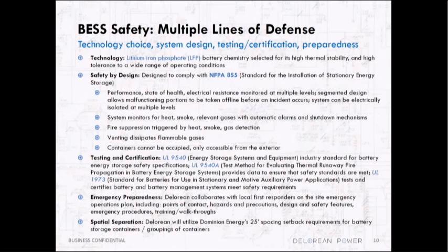Dominion Energy requires battery projects to site containers or groupings of containers up to 8 megawatt hours in energy density 25 feet apart. This significantly limits the risk of fire contagion from one container to another, isolating a fire event in the unlikely situation one occurs.